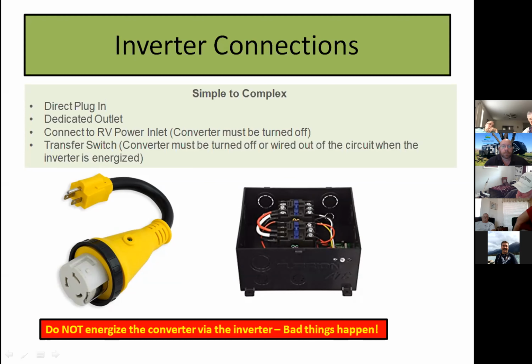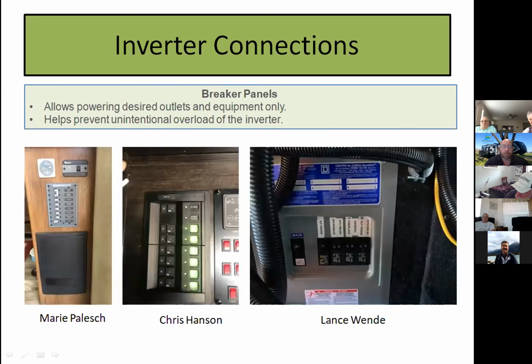Even with a transfer switch, you're still going to have the converter turning on, so you'll need to make some changes to your wiring. You need to put in a relay to shut your converter off, or install a separate set of circuit breakers that allow only certain dedicated circuits to be powered on.